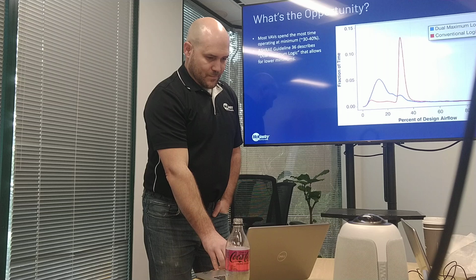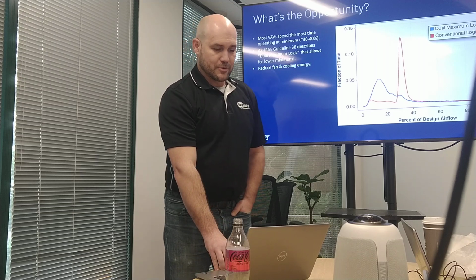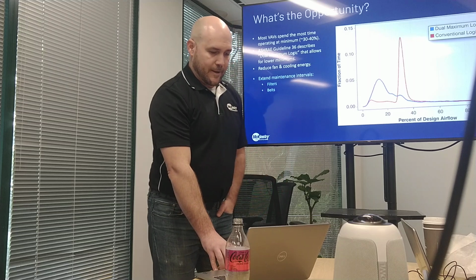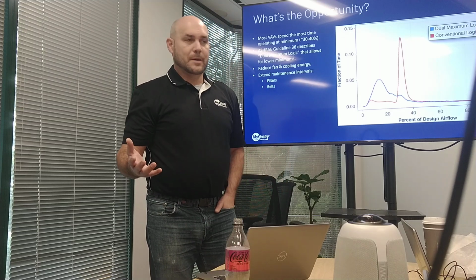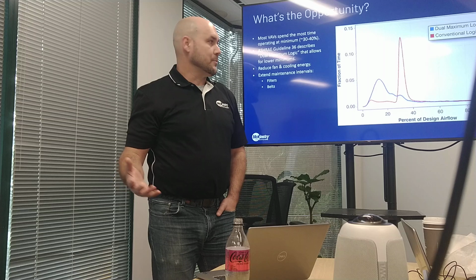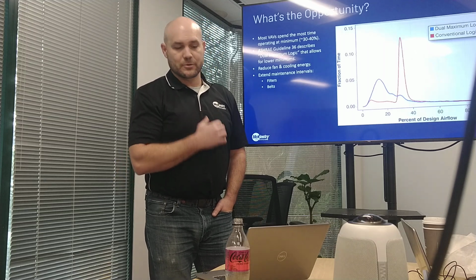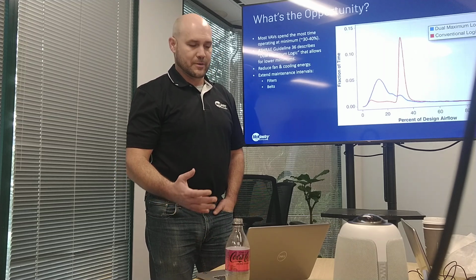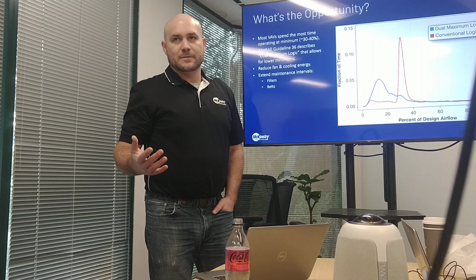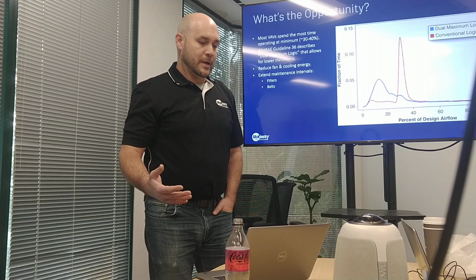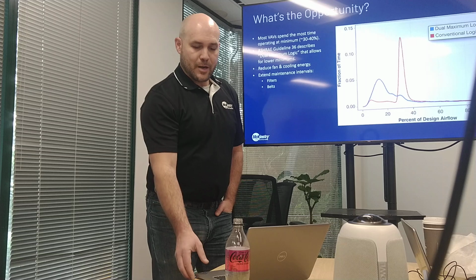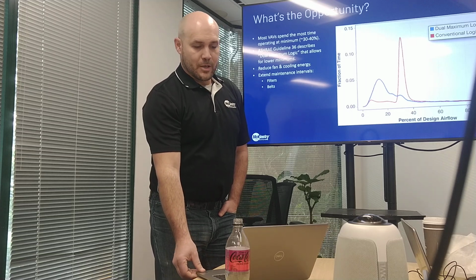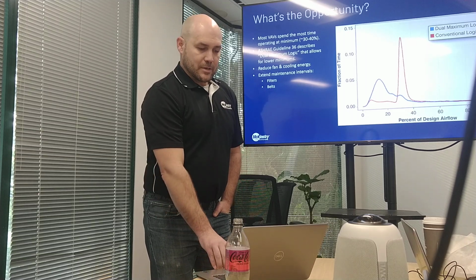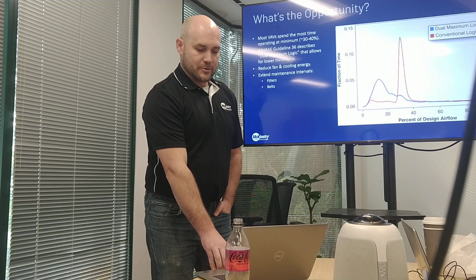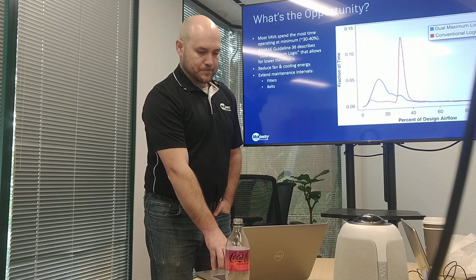I had all these animations. So, reduce fan and cooling energy. I guess it also has the opportunity, from an operation standpoint, to extend maintenance intervals for fans, filters and belts, because the fan's not running as hard. You're not moving as much air across filters, so it stands to reason that filter intervals and belt intervals would be extended.